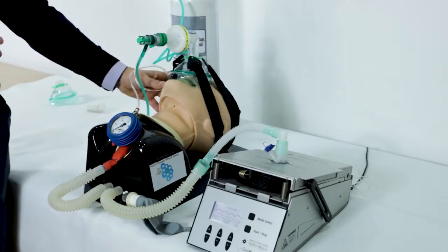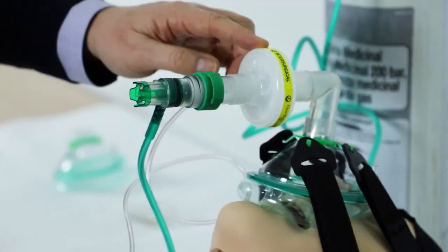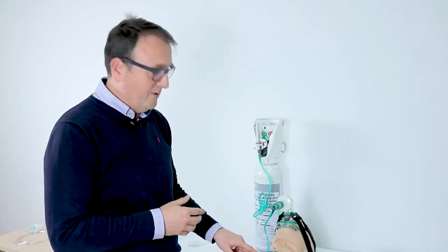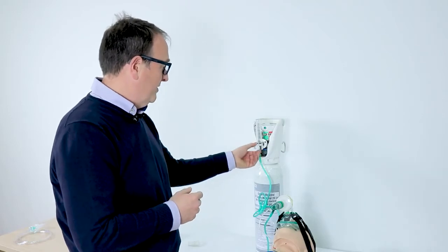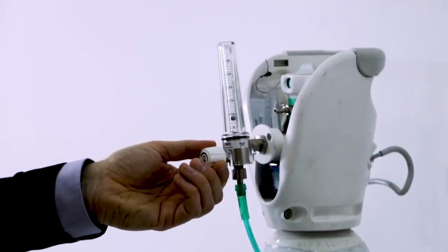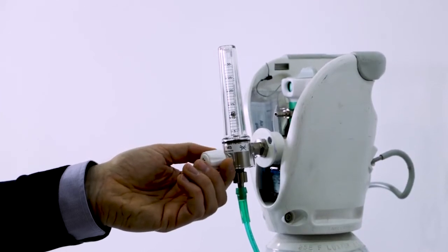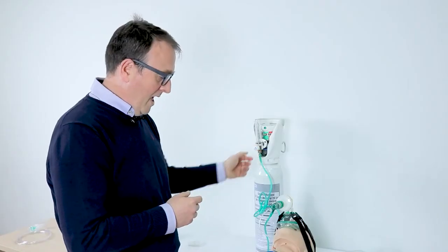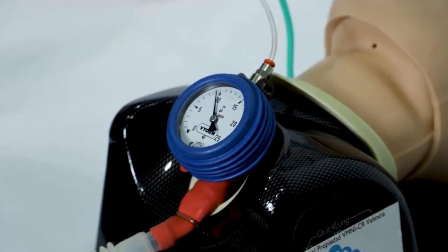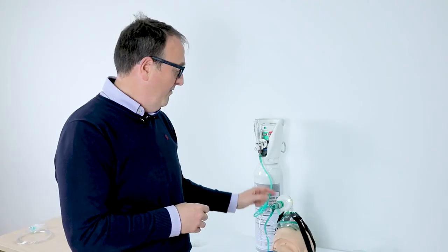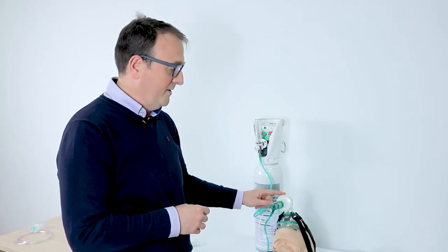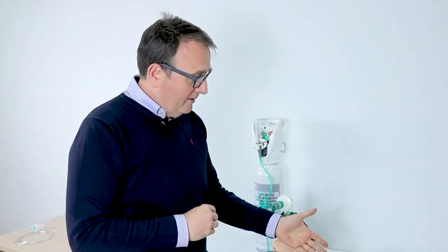So this is the system assembled in a simulated lung. So we have a mannequin here, and here we have the mask, the filter, and the Boussignac valve. Also, it's important to connect the manometer for pressure monitoring. I'm going to show you one important figure, that is when I increase the flow up to almost 15, you can see the lung here. So there is a perfect transmission of the pressure from the Boussignac valve through the filter directly to the lungs.